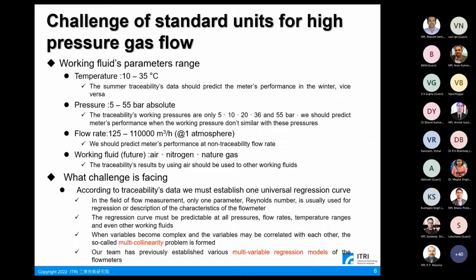The challenges for this paper were as follows. There were many variables with big ranges, such as temperature from 10 to 35 degrees Celsius. The summer traceability data should predict the meter's performance in the winter, and vice versa. Pressure ranges from 5 to 55 bar absolute. The traceability working pressures are only 5, 10, 20, 36, and 55 bar. We should predict the meter's performance when the working pressure is not similar to these pressures.